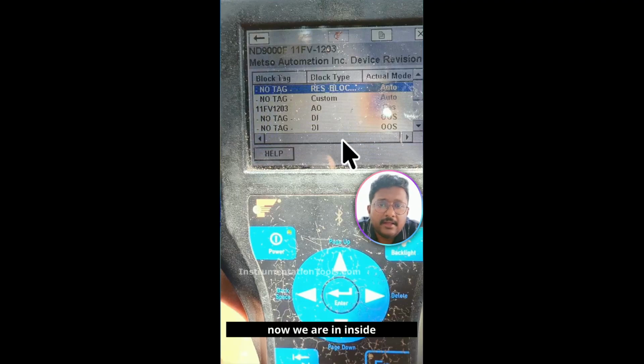See, now we are inside the 11FV1203. This is a Metso valve positioner. Inside your fieldbus settings, you will find different blocks like resource block, transducer block, analog input block, analog output, digital input, digital output, PID, etc. In this case, this is the analog output, right? It is using digital communication, but we call the blocks analog input, analog output, based on the type of instrument. It doesn't mean that we are using a 4-20 milliamp signal. We are using only digital communication between your Foundation Fieldbus instrument and DCS system.